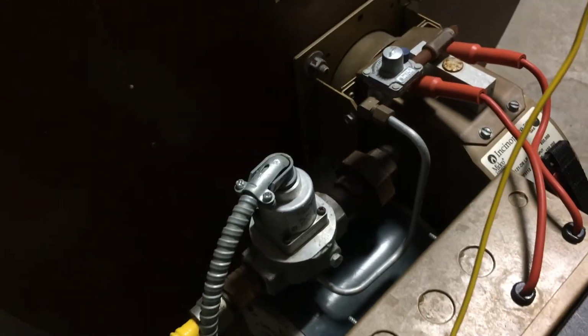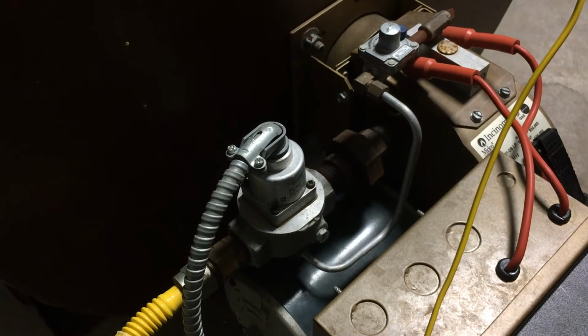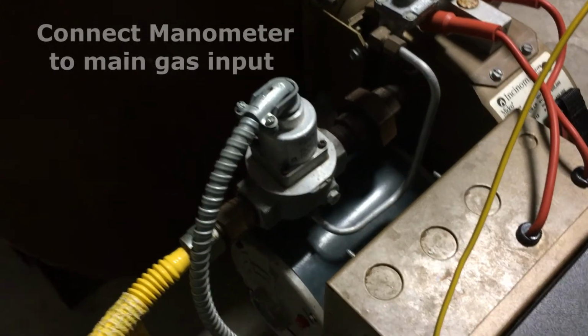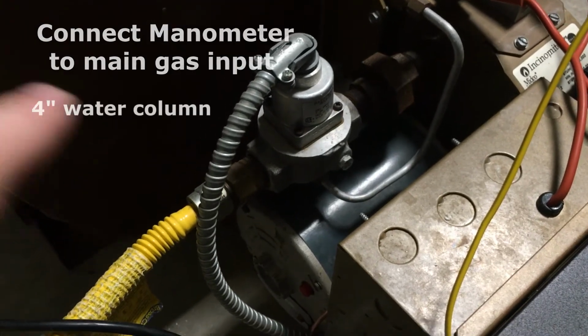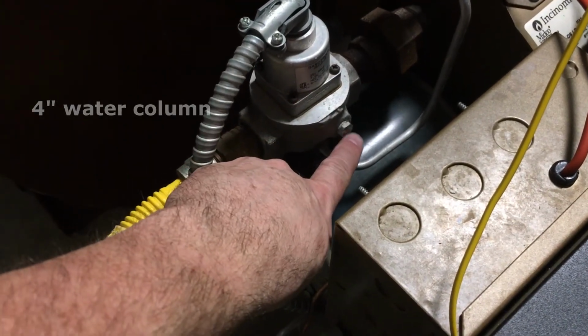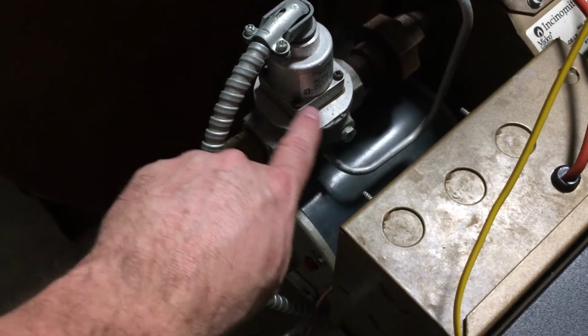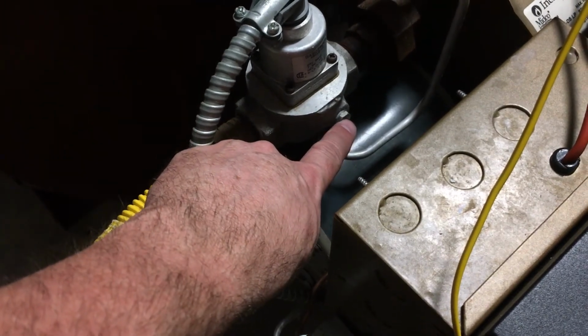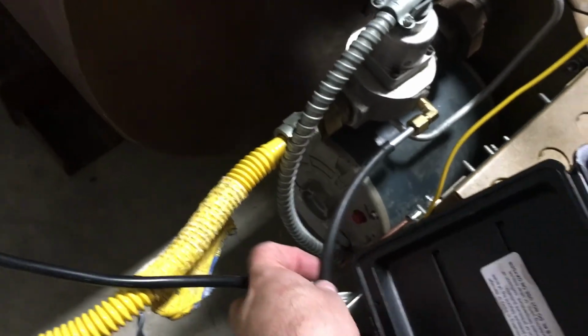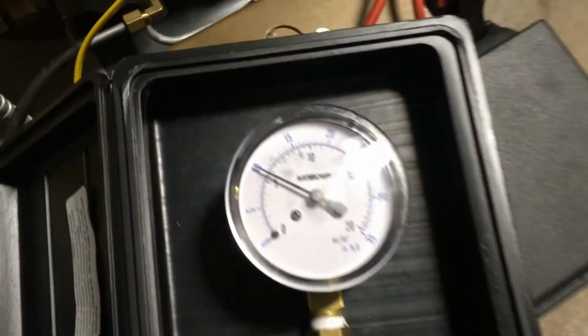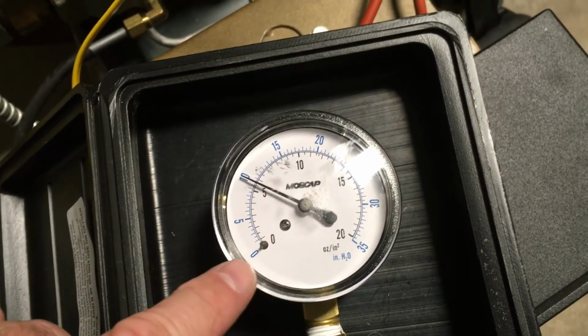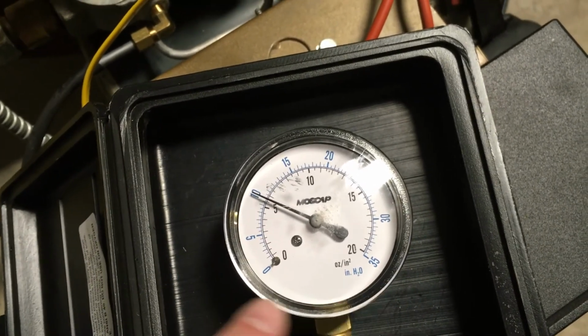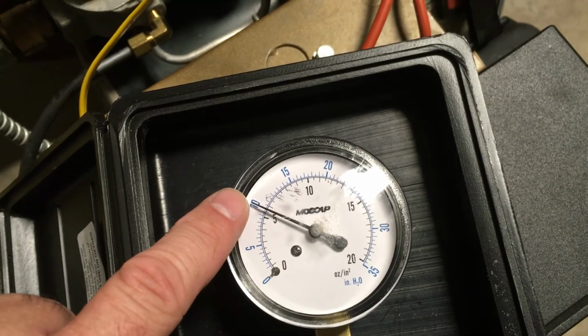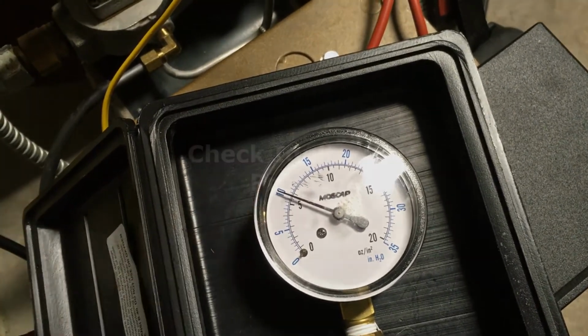Now that we have checked all the voltages going through the system, we need to verify gas pressure accordingly. So we're going to connect the manometer to the main gas input to verify we have 4 inches of water column. On the main gas regulator, there should be a test port on the side of it. There may be different valves, but each valve should have a test port. So we're going to connect to this test port with a manometer. You can see I hooked up some fittings to show that we have a manometer connected up. I turned on the gas supply, and in here you can see that the blue outer is listed in inches of water column. So we do have 10 inches of water column of pressure. You need a minimum of 4 inches of water column. So we do show that we have the proper incoming pressure right now.